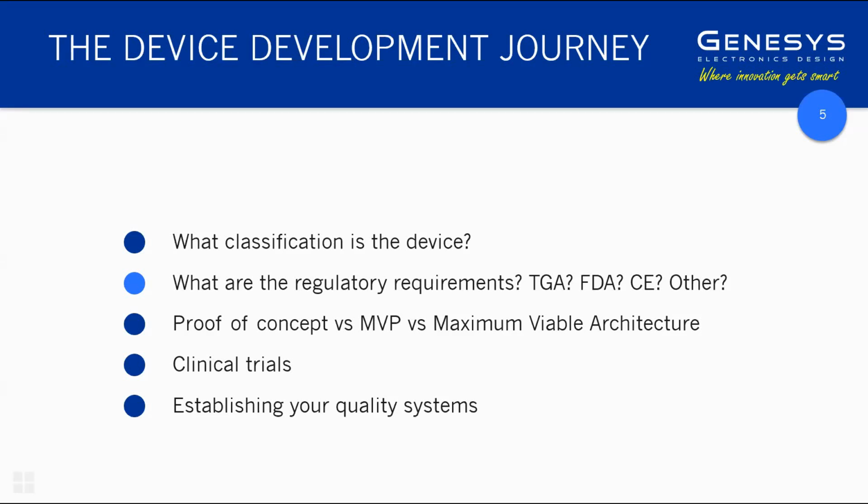There's a lot of confusion around what a proof of concept device is. People tend to confuse proof of concept with engineering prototype, because the engineering prototype is on the pathway to what will become the commercial product, whereas often a proof of concept is a very simplistic device and in many cases a throwaway device. So it's really important not to set your heart on doing a proof of concept as a quick and dirty way to prove the bare minimum viability of your concept and expect that to follow through to ultimately evolve into your deployable product.